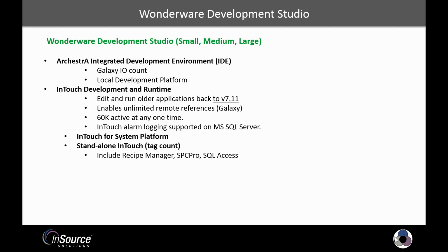We can also use this license and place that onto a machine that has an older version of InTouch, and it will still enable that older version of InTouch with our newer license. So the license is backward compatible for development. And a development license doesn't distinguish between an InTouch for System Platform or a standalone or modern InTouch application. That is done on the runtime end once we're finishing developing. So again, this development studio is for the development of an application, not for the runtime, but there will be one exception that we'll see in a little bit.